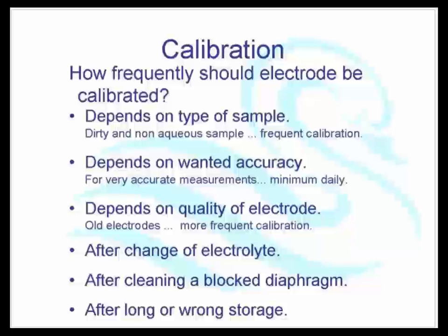Those of you that have dealt with pH probes know that basically a pH probe is a nightmare. You need to calibrate it, well, once a day, probably. At least once every 3 days. If you can get away with once a week, then you're lucky.